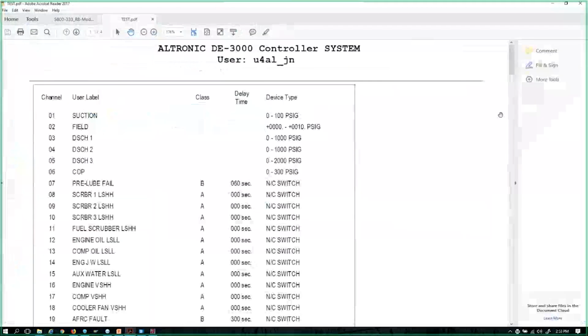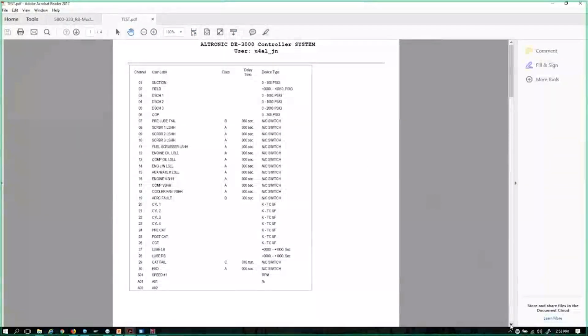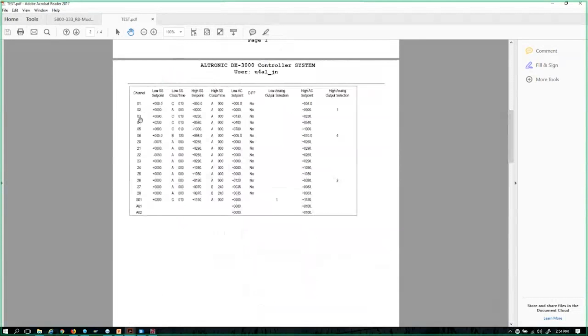So there the document is, and I'll open it up for a moment. And this is a handy document if you're a commissioning tech or just trying to cover your tracks when you've been doing a project out in the field. But it tells you the channel number, the user label, the channel class, the time in seconds, the device type. The second page tells you a little bit more detail what your low shutdown point is configured as, your high shutdown point, so on and so forth.